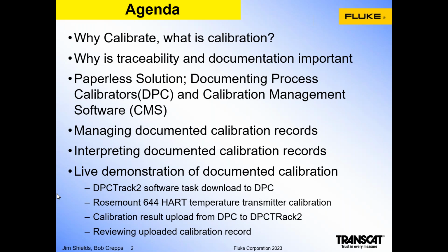The calibration management software, the CMS, that he's going to be demonstrating is called DPC Track 2, and he will demonstrate downloading a software task to a documenting process calibrator, or DPC. That task is downloaded by tag number. That tag number will be for calibration of a Rosemount 644 thermocouple temperature transmitter, and he's going to pull up that task in the calibrator and do a calibration on that transmitter.